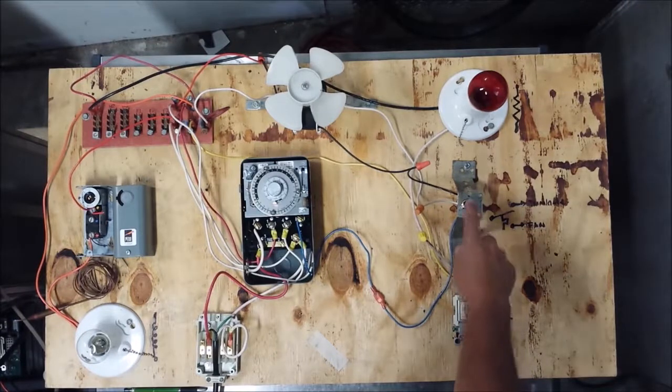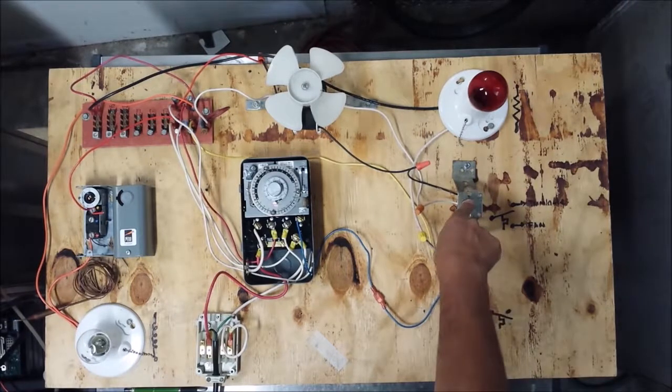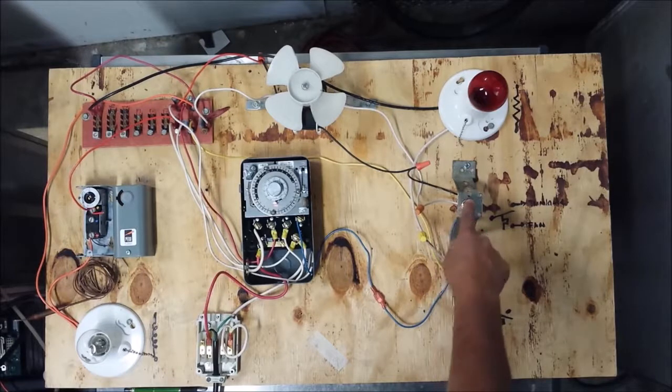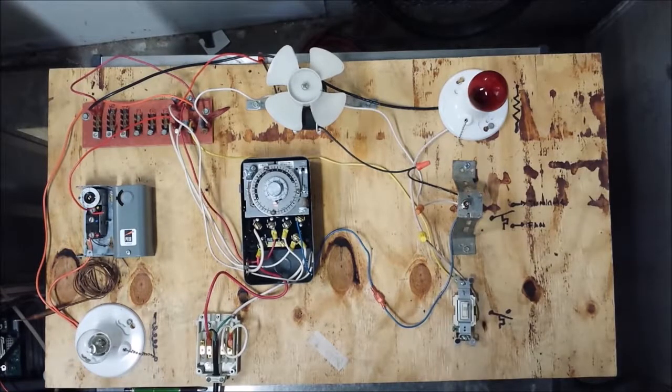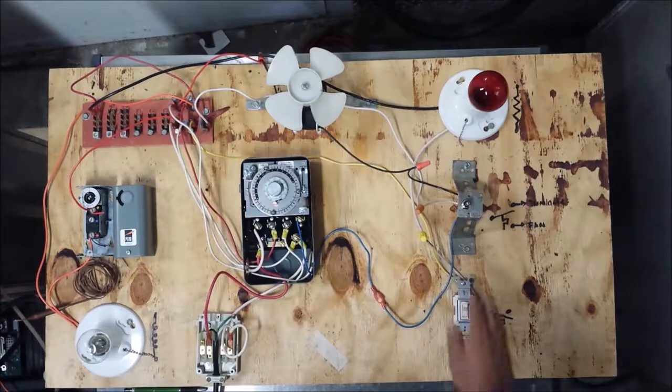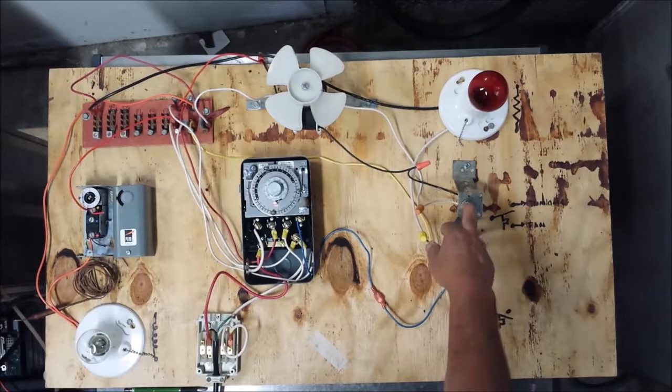We have a DTFD control, which is this little switch. It indicates a defrost terminate / fan delay thermostat control. The purpose of that is to allow the fans to not come on until the evaporator temperature drops, and once it drops, that switch closes and then the evaporator fans will come on. It's got another thermostat within it, and that's the defrost terminate portion of it.